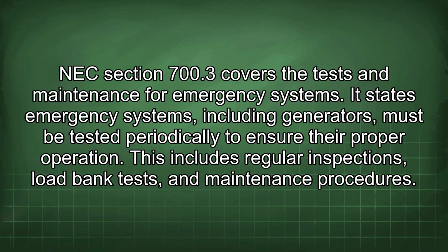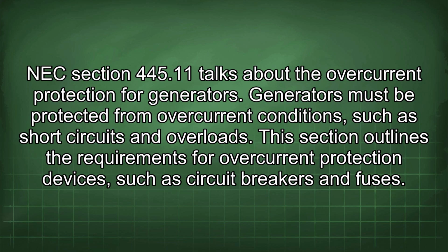NEC Section 700.3 covers the tests and maintenance for emergency systems. It states emergency systems, including generators, must be tested periodically to ensure their proper operation. This includes regular inspections, load bank tests, and maintenance procedures. NEC Section 445.11 talks about the overcurrent protection for generators. Generators must be protected from overcurrent conditions such as short circuits and overloads. This section outlines the requirements for overcurrent protection devices such as circuit breakers and fuses.